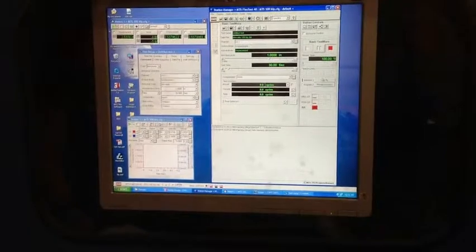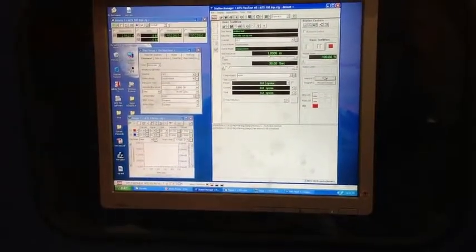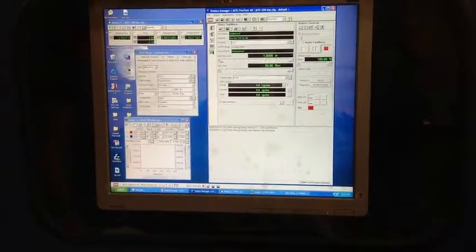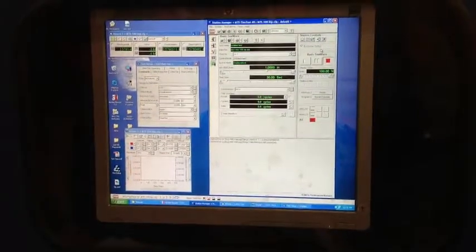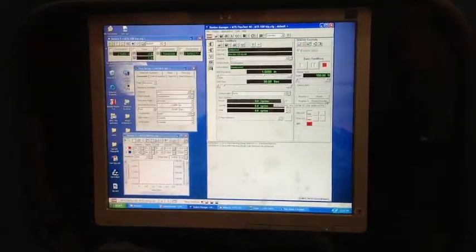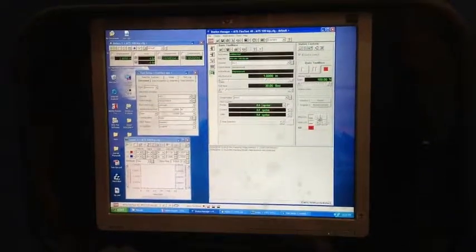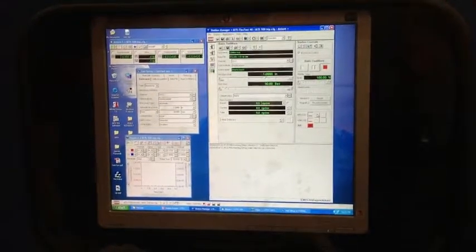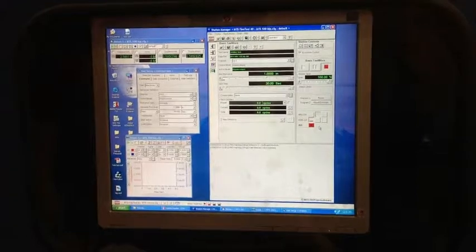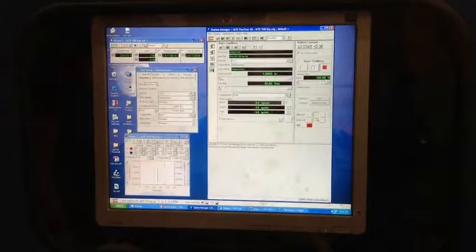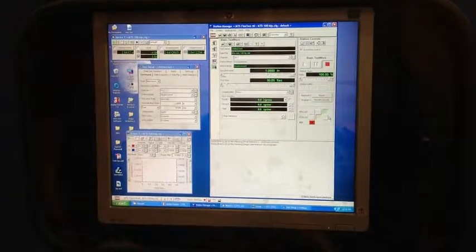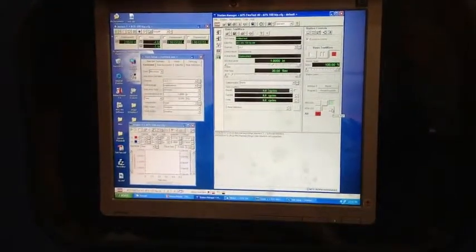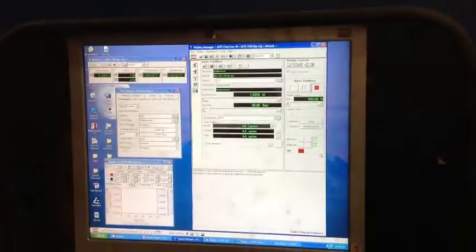First thing first, you will need to hit reset to make sure all the interlocks are reset. Then you click on this checkbox. This is to enable the exclusive control. So after that, you can turn on your pumps. And you will need to follow a certain order. So the order will be you click on HPU J25 power low first. Then you go to HSM J28 power low. Then will be HPU power high. Then HSM power high.